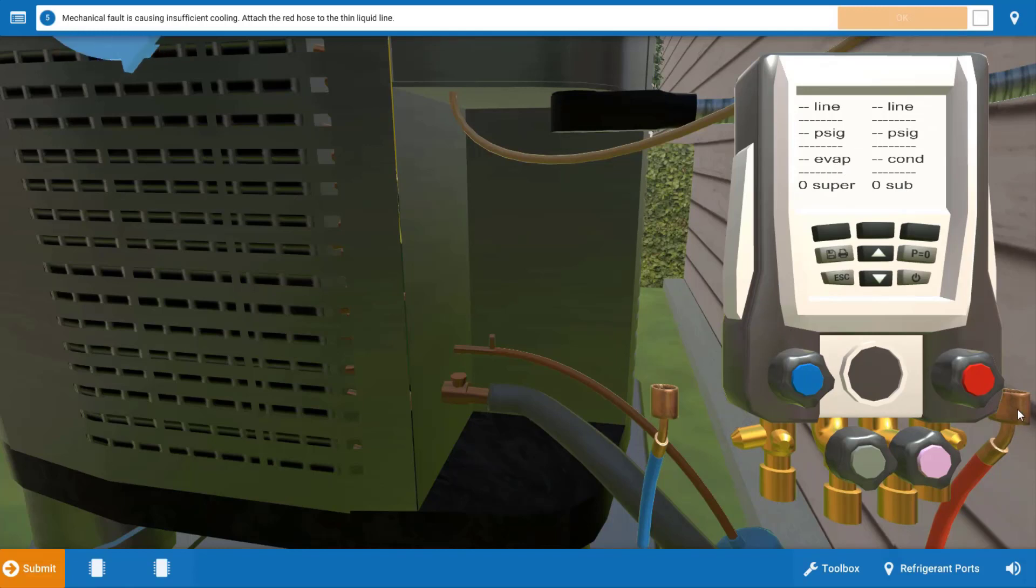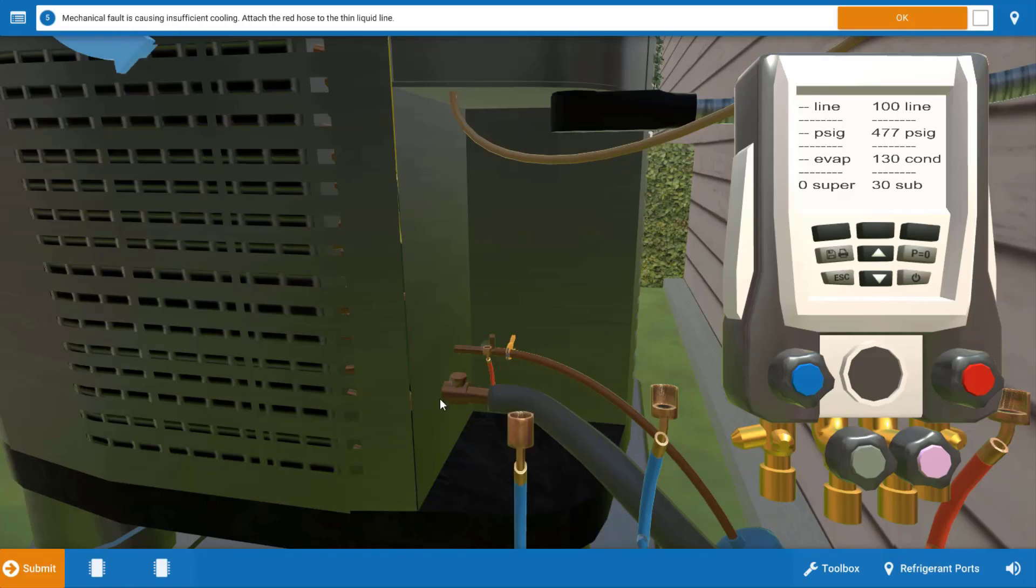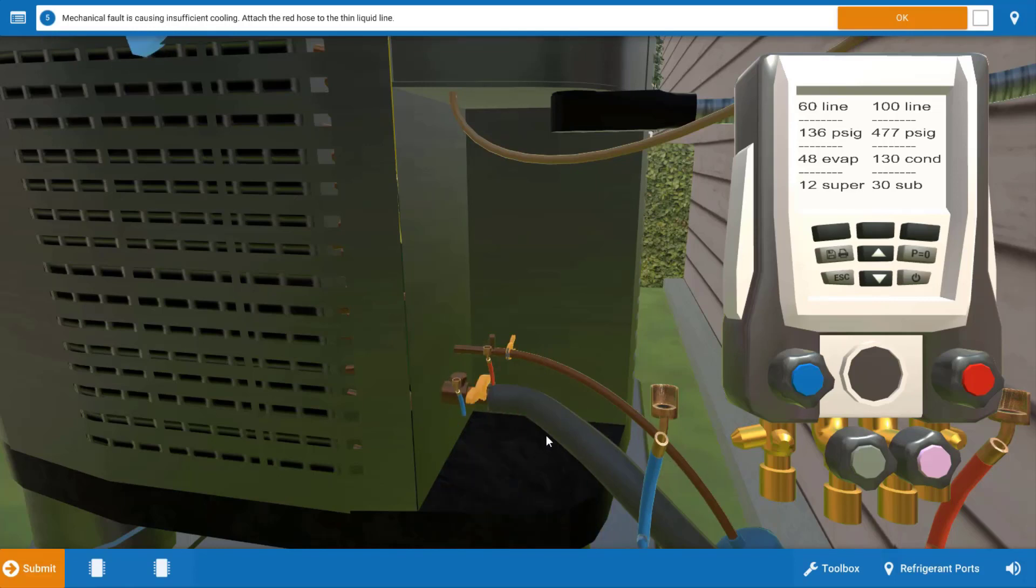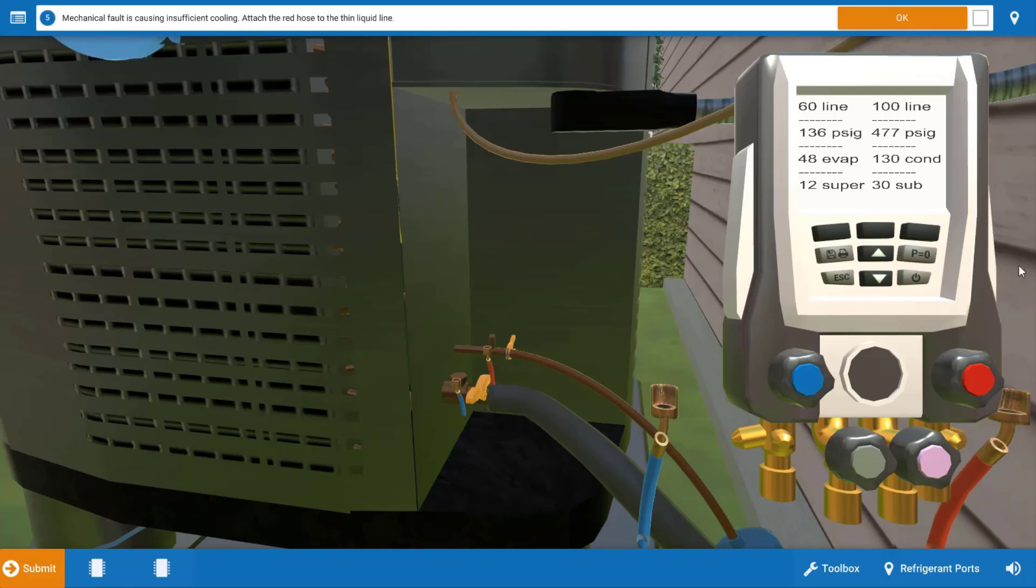We're going to start by attaching the red hose to the liquid line service port. This is the high pressure connection and will also attach a clamp thermometer. We're going to attach the low side hose to the suction service port which will give us our low side pressure. This will also provide us with our suction line temperature with this convenient clamp probe here. These digital gauges will calculate everything for you, so let's take a look.